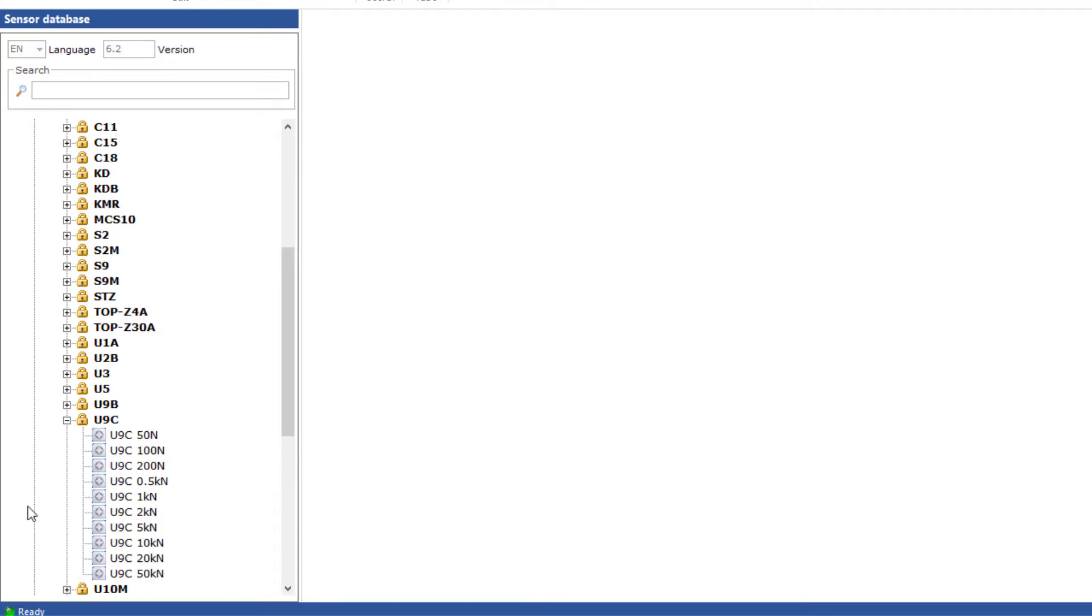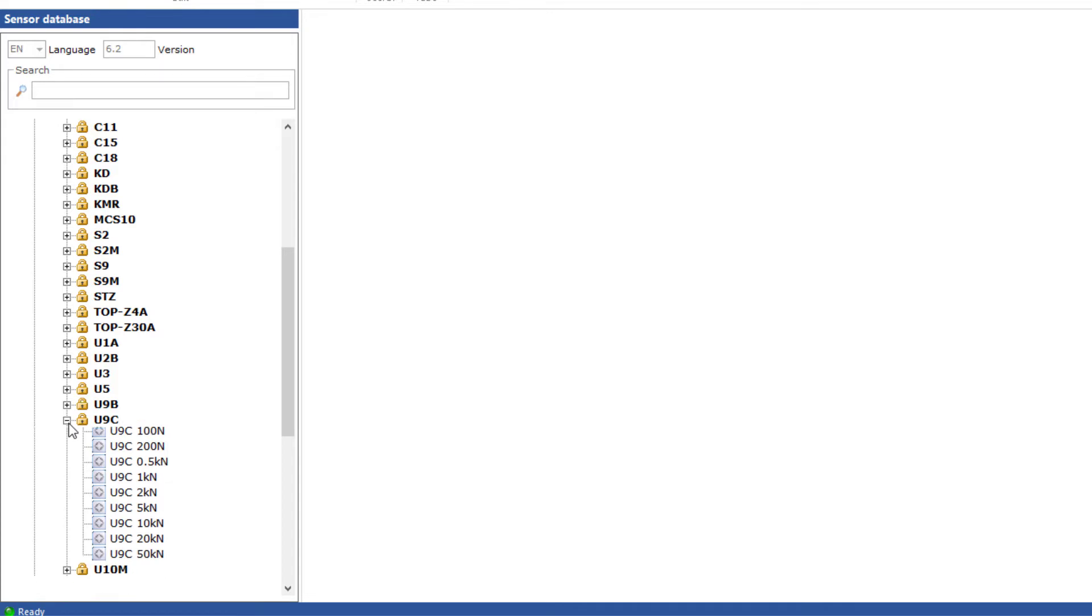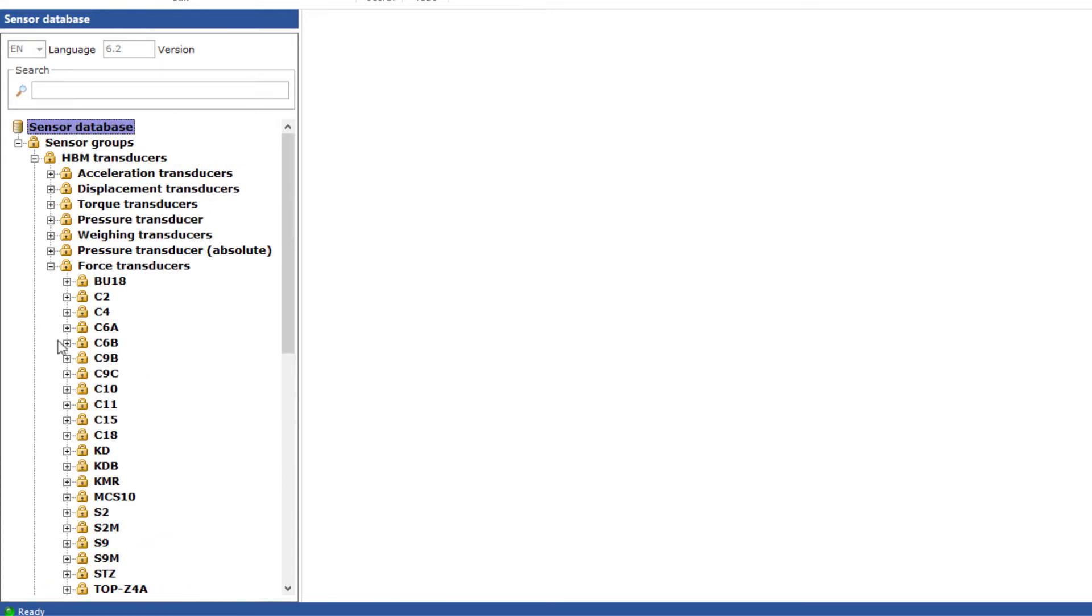However, it would be wrong to simply change the sensitivity value of the already created sensor U9C 100N. If you later purchase another sensor of the same type, it will of course have a slightly different sensitivity value. This would lead to conflicts. Therefore, these sensor groups are protected, hence the lock.